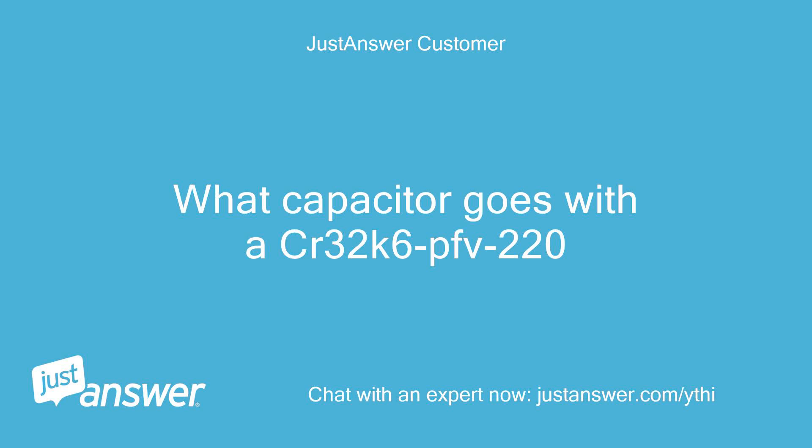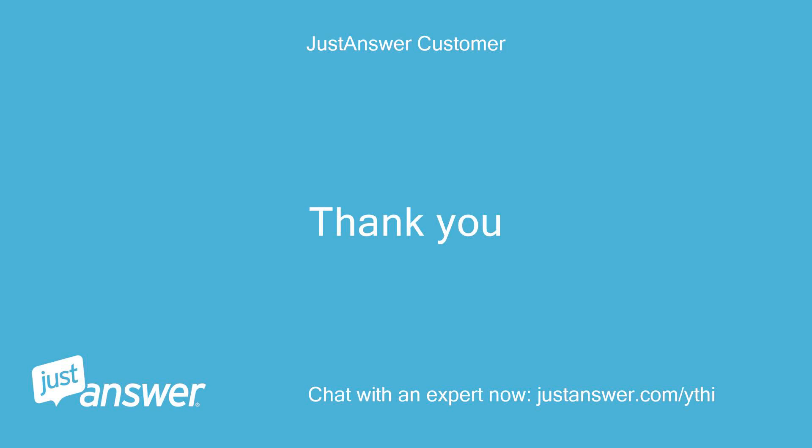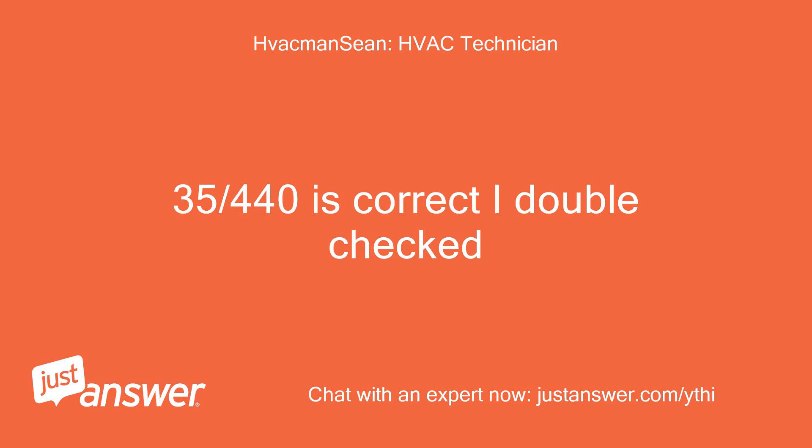What capacitor goes with the CR32K6PFV220? Should be a 35MFD. Thank you. Be sure to rate me so I can be paid for helping you, thank you. 35-440 is correct, I double checked.